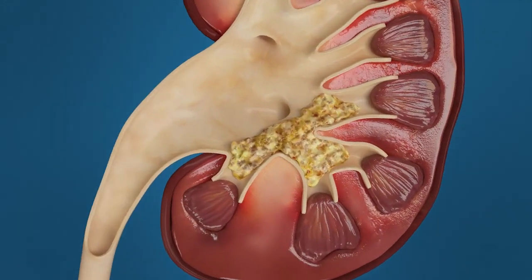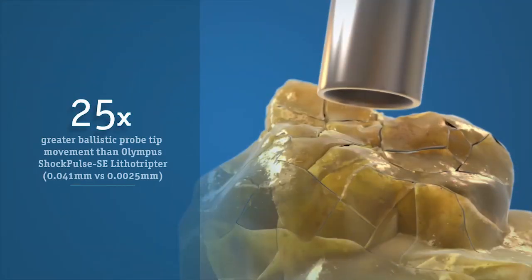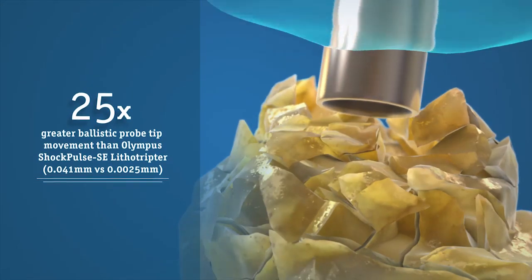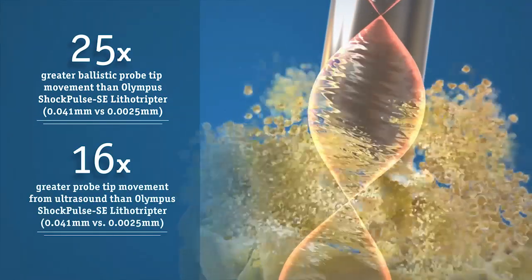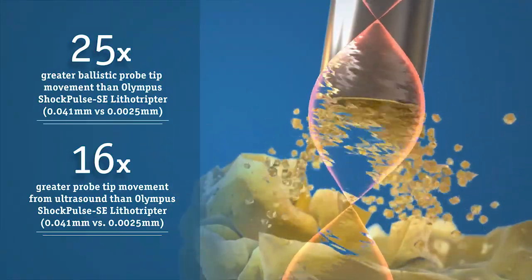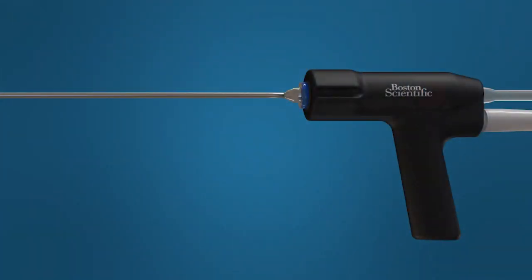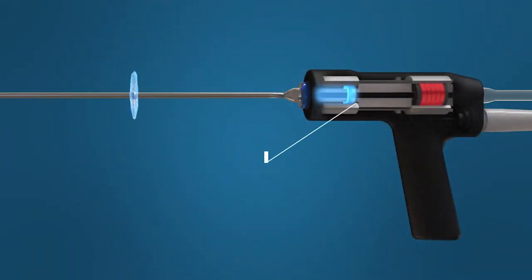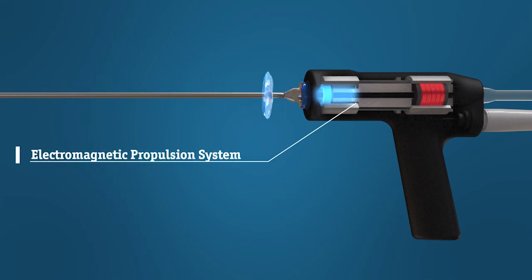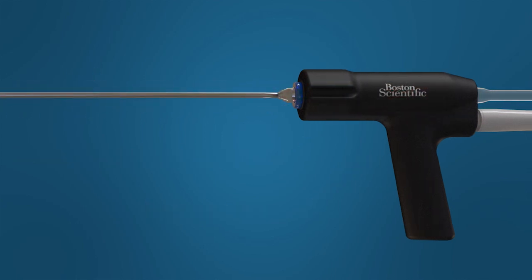The Lithoclast Trilogy Lithotripter can efficiently treat hard stones. Ballistic energy can fragment hard stones while the ultrasound grinds down stones into finer particles for removal. With the energies delivered through the movement of the probe tip into the stone, the Trilogy Lithotripter's proprietary electromagnetic propulsion system generates controlled ballistic energy simultaneously or independently with ultrasound energy to deliver powerful fragmentation.